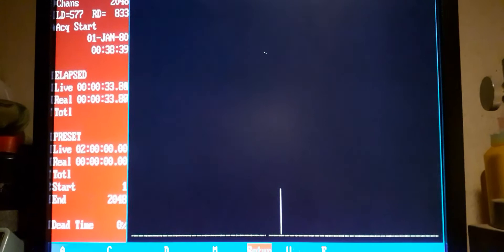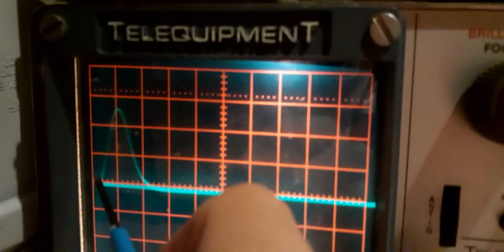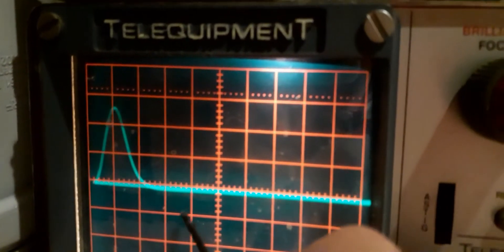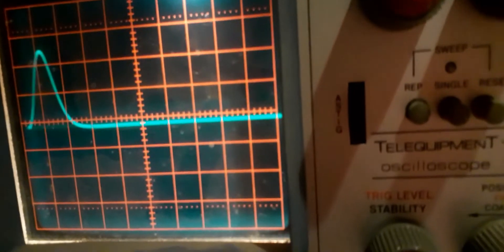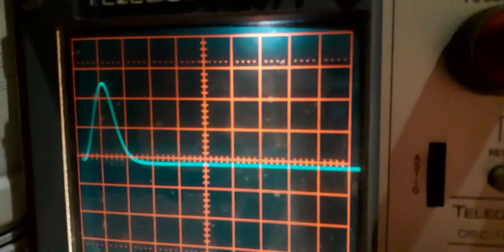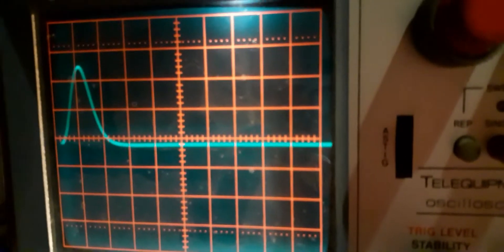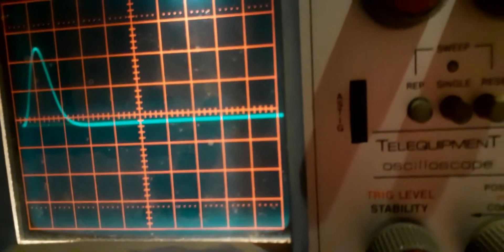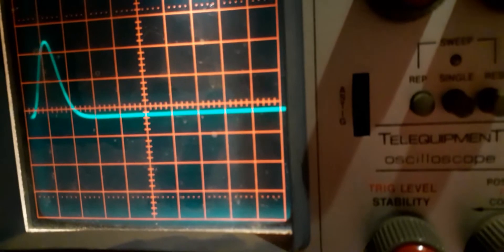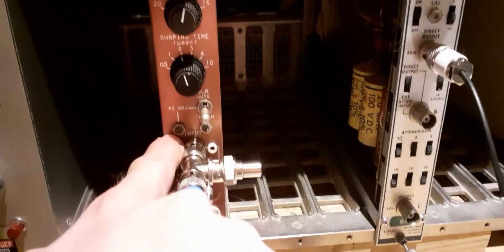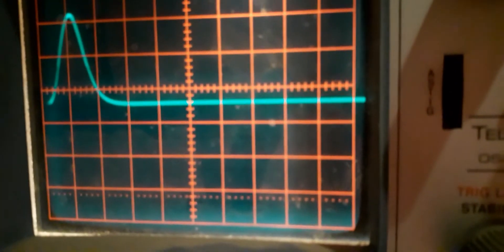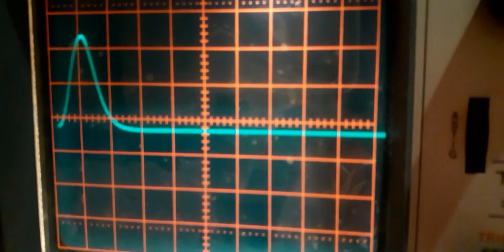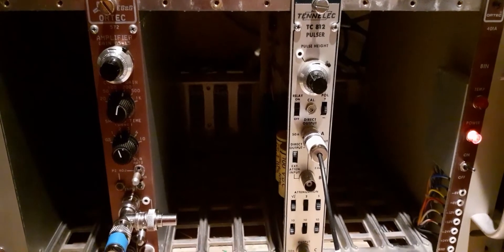Now there's a little drift and you'll see that because all of this NIM electronics needs to warm up—really you should have left it on half an hour before you want to use it. This is exactly how you tune all of this electronics. If you have an undershoot, like a pulse that was kind of bipolar with a negative segment before returning to the baseline—this is called undershoot and it's undesirable—what will happen is if the next pulse lands on that tail, then the next pulse will look lower to the electronics than it actually is. That'll give peak broadening, and you can compensate for that with a pole zero adjustment circuit. I have both one in this spectroscopy preamplifier and I've also built one in here. I'm using both of them to make this peak nice. Once again, I'll do a comprehensive video on that at some point.